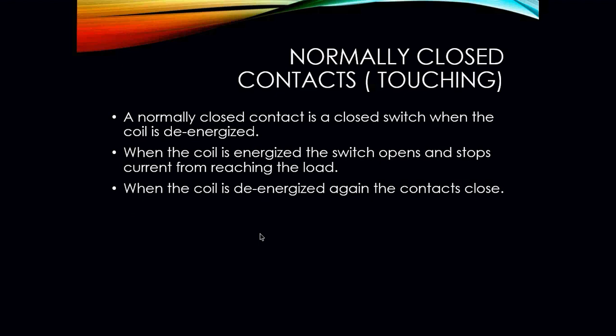The term normally closed describes contacts that are in their normal position when the coil is de-energized. When the coil is energized, that contact is now going to open, which turns off the voltage. Therefore, it's going to shut off a load. And when that coil is de-energized again, those contacts will close. Remember, once the coil is energized, our normally open and normally closed contacts are going to do the complete opposite. Our normally closed are going to open. Our normally open are going to close.